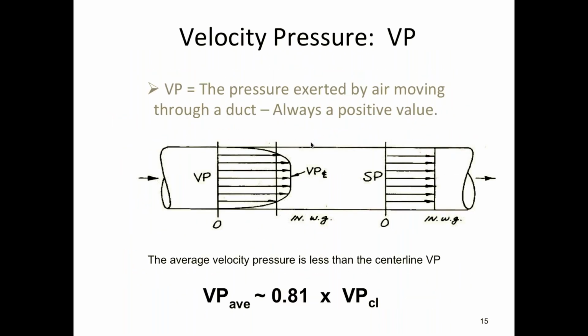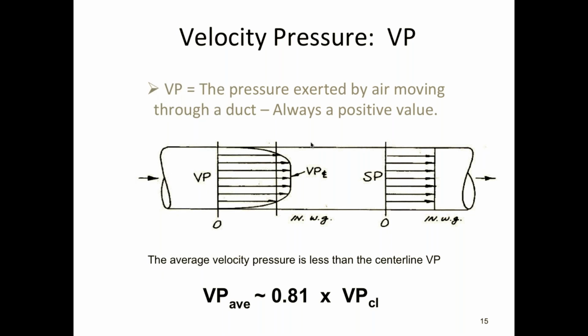Okay, so now air doesn't move linearly through a duct system. At these velocities there's something called turbulent flow and laminar flow. Laminar flow is when fluids are moving very slowly and the whole thing is moving at the same rate, with no eddy currents, moving straight through. That's not what's happening in here. This is moving very quickly. There's friction on the outer edge where the air is hitting the duct wall. So the flow through here is turbulent and uneven. In the middle of the ductwork, the air is moving faster than it is on the outside. So it looks like this bullet-shaped curve that shows the rate the air is moving through here. It's shown as velocity pressure right now, but that's really the way the air would be moving. We have to be cognizant of that because it affects how we measure the amount of air moving through here.